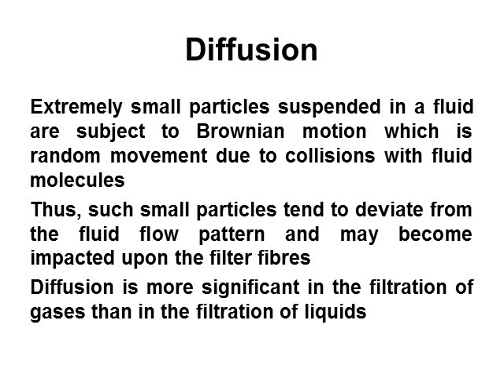Diffusion: Extremely small particles suspended in a fluid are subject to Brownian motion, which is random movement due to collisions with fluid molecules. Thus, such small particles tend to deviate from the fluid flow pattern and may become impacted upon the filter fibers. Diffusion is more significant in the filtration of gases than in the filtration of liquids.